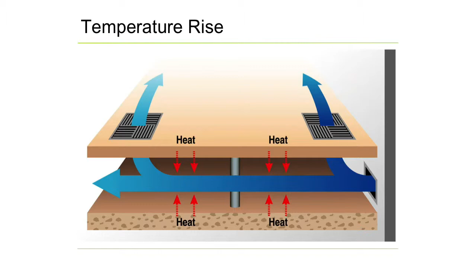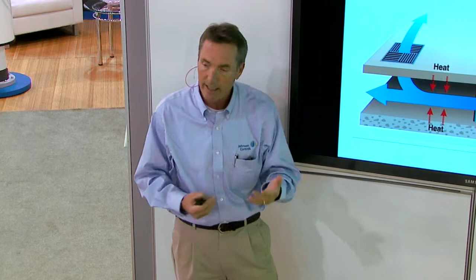So 1.2 has changed, it's also reflected in the book. This is what I mentioned earlier, the whole thought of how do we control temperature under the floor. A good rule of thumb is that from where the air enters the plenum, or underfloor air handling space, to the furthest diffuser, we want to maintain no more than about a 3-degree rise in temperature. That typically equates to a comfortable space. If you get into 5, 6, 7, we've seen 10-degree changes, that's a problem in terms of pure comfort.